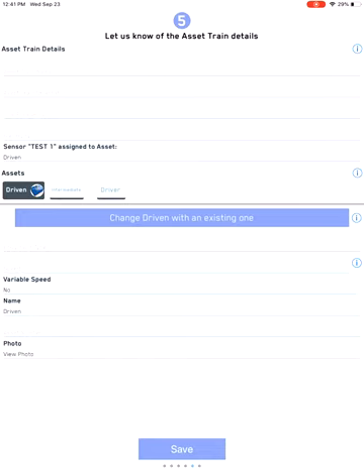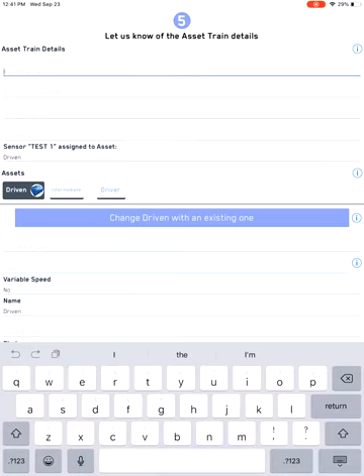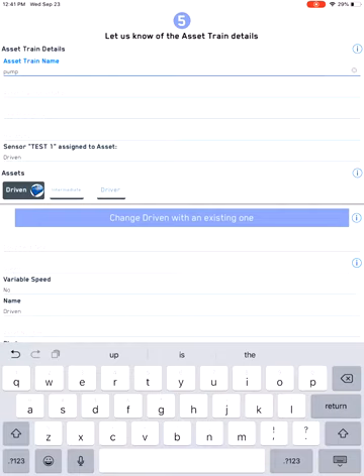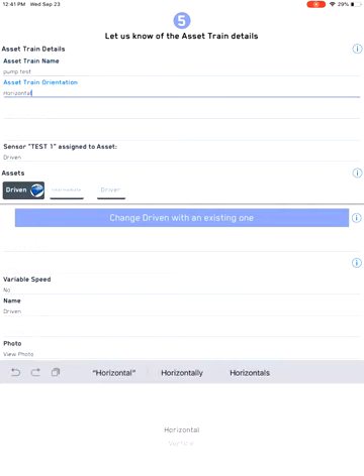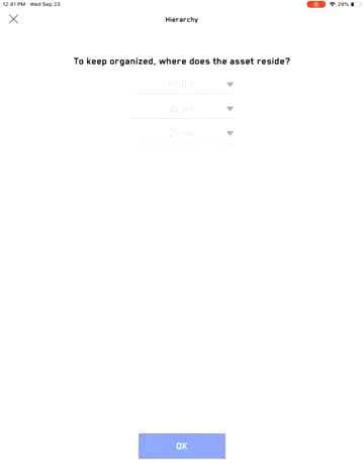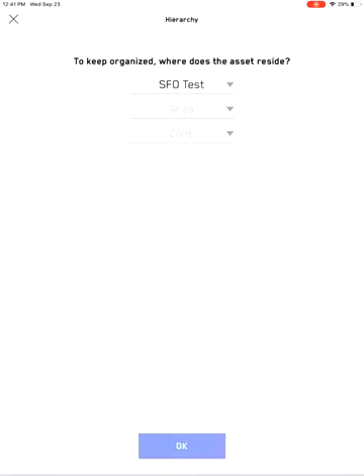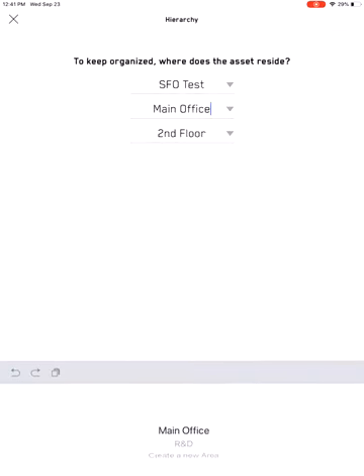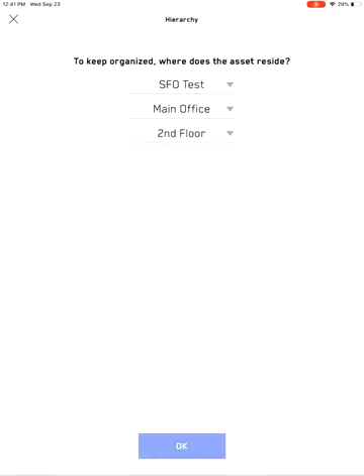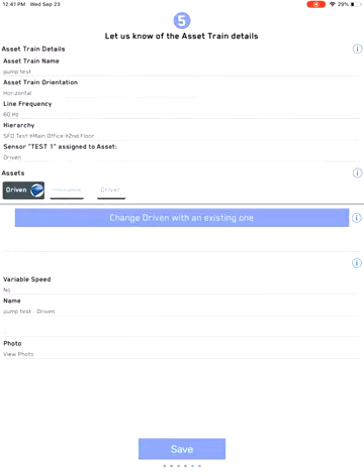But for right now, we will be associating the sensor to an asset train. So the asset train consists of your driven, driver, and intermediate. For this particular case study, we'll just name it as pump test. And then the next thing would be the orientation, which is horizontal or vertical, line frequency usually 60 hertz for all of America. And this is where it's also important because you want to know where in your account do you want to associate this to. Make sure that you associate to the right area, to the right plant, and to the right zone.